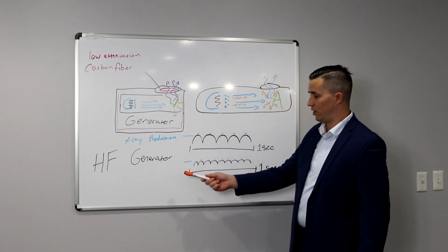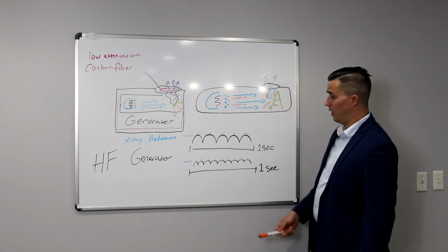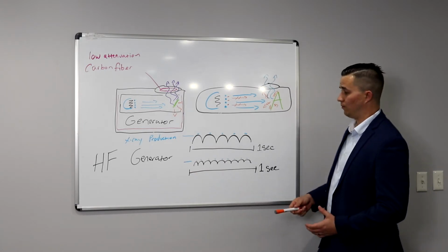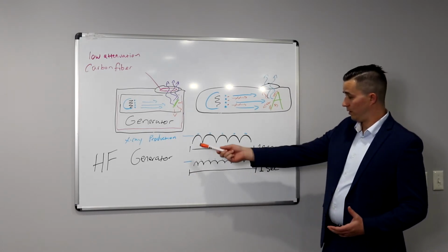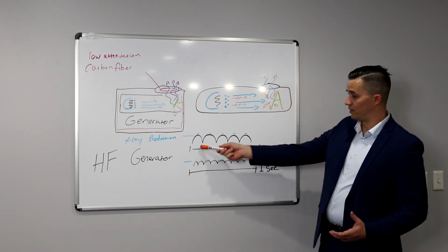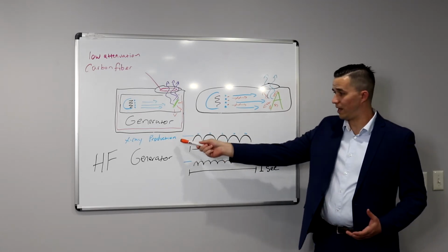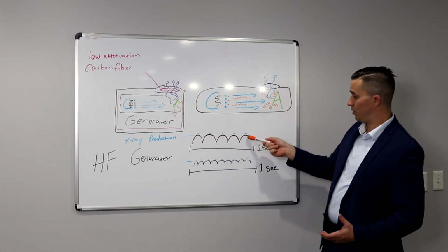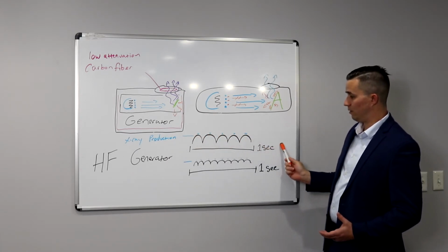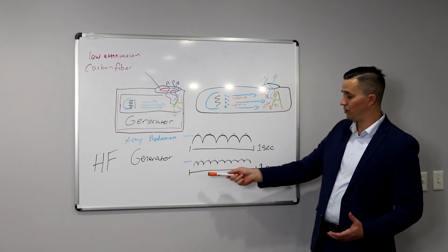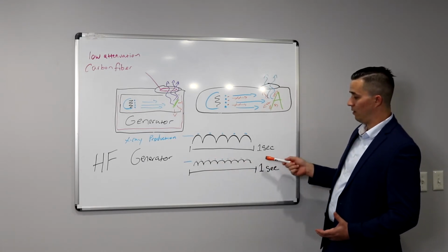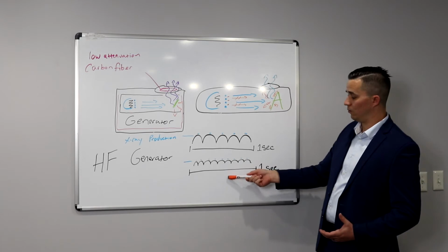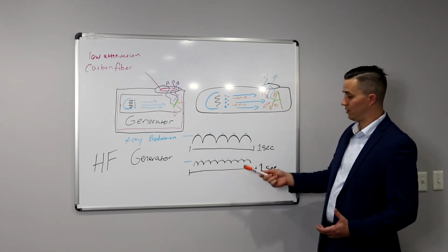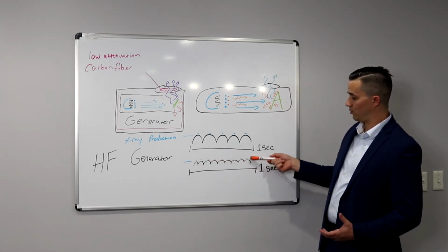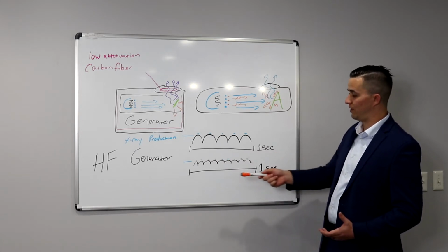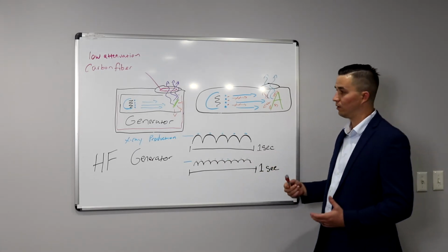We use a high-frequency generator. It's patented technology, and not all are created equal. We'll see here in the top example that the high-frequency generator in this instance can make X-rays at the line of X-ray production 5 times per second. With this generator, it would be doing it at twice that speed. So this generator would be more efficient because it's producing more peak X-ray production per second. That means it's able to ramp up power much faster.